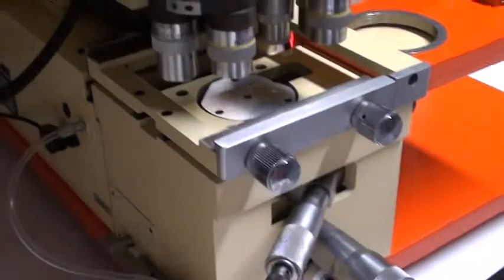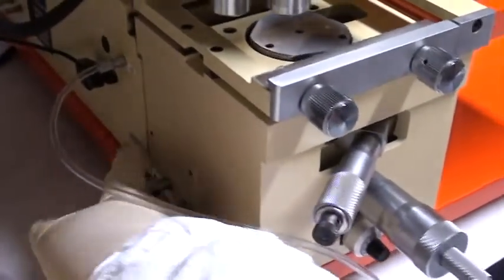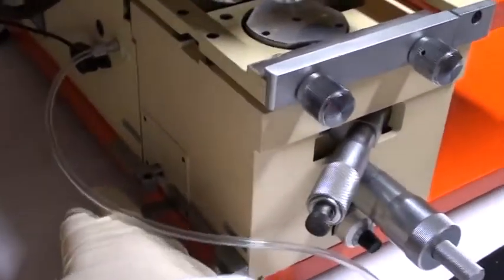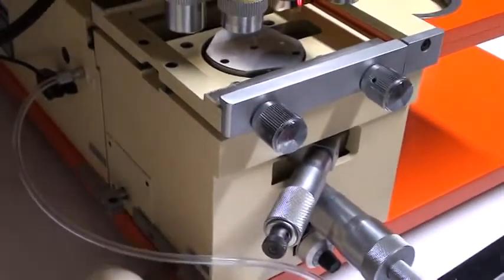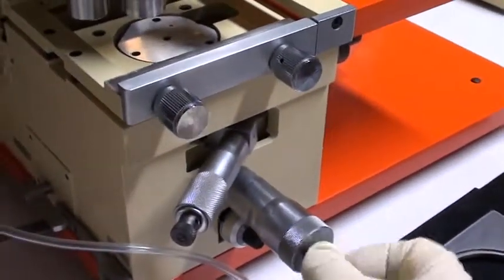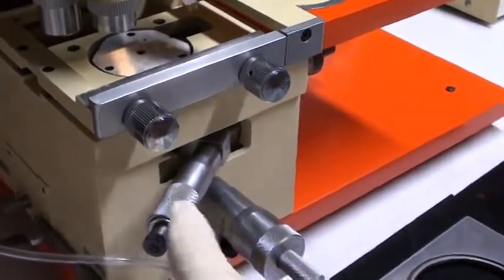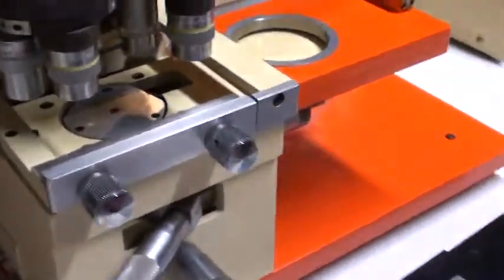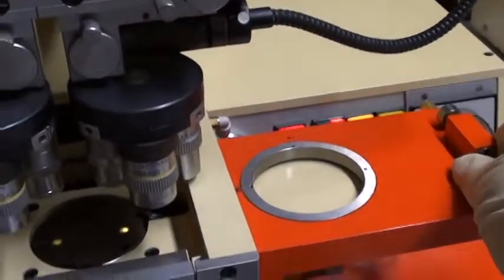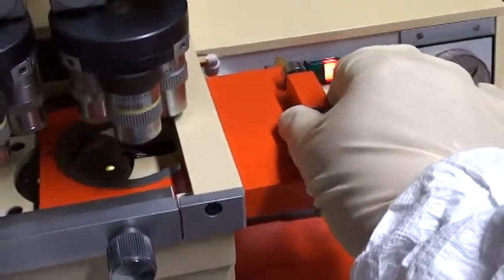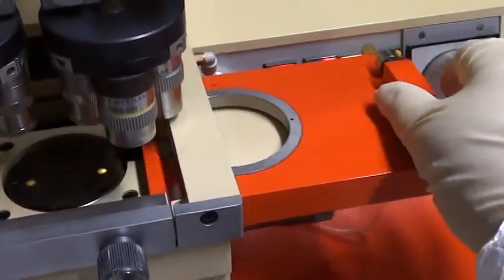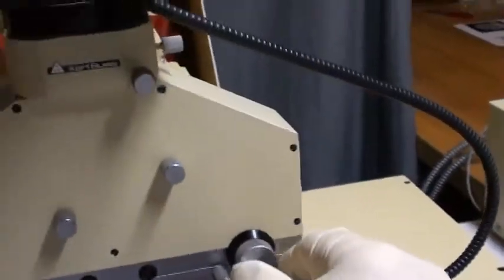In operation, the machine contact lever raises the chuck. This will allow you separation for doing your alignment. You can see that the micrometers are all functional, smooth, have been cleaned and adjusted. The same with the wafer transport light. All new bearings have been installed, complete alignment has been done, and the same with the microscope.